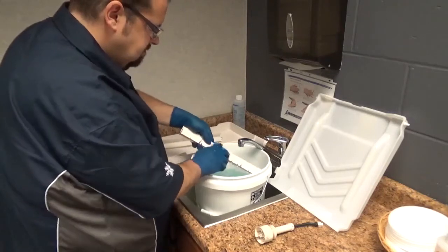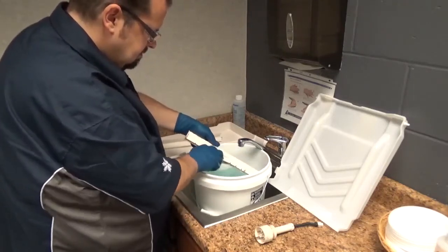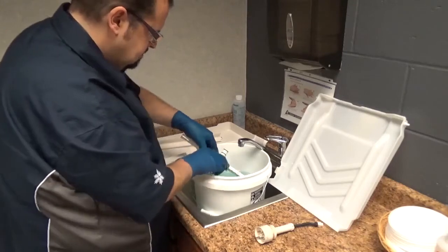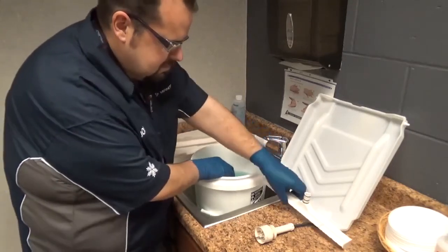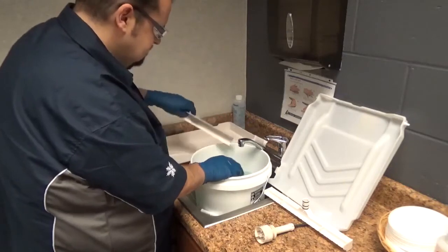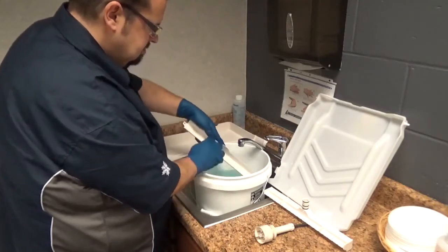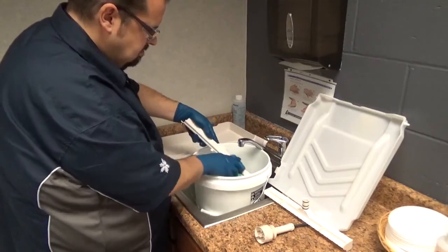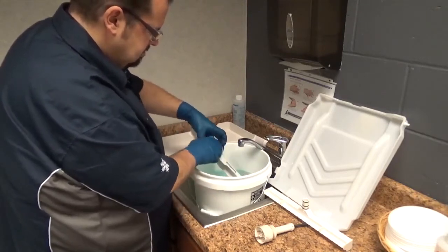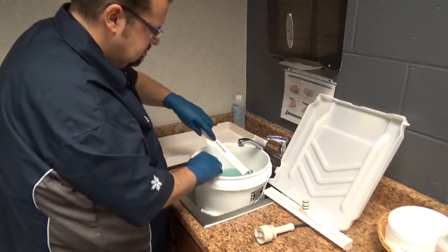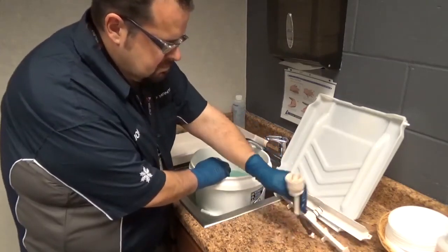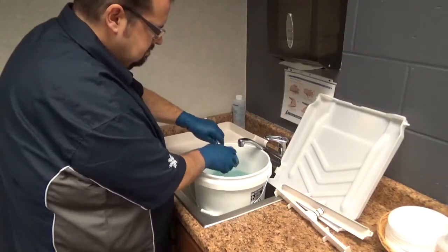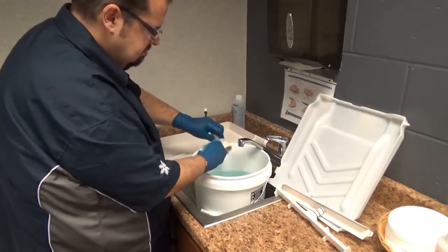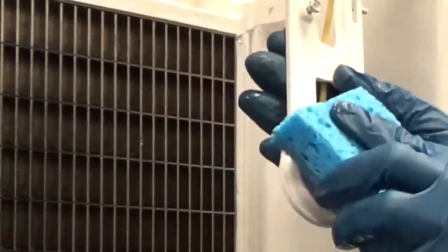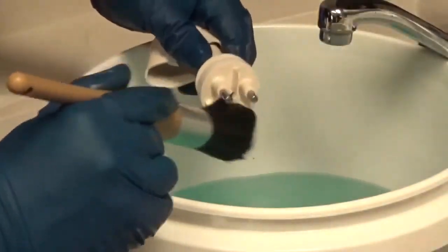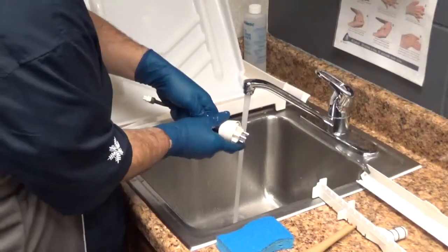Step 7. Use half of the cleaner and water solution to clean all components. The cleaner solution will foam when it contacts the limescale and mineral deposits. Once the foaming stops, use a soft bristled nylon brush, sponge or cloth, but not a wire brush, to carefully clean the parts. Soak parts for 5 minutes or 15 to 20 minutes for heavily scaled parts, with the exception of the ice thickness probe and the water level probe. Rinse all components with clean water.